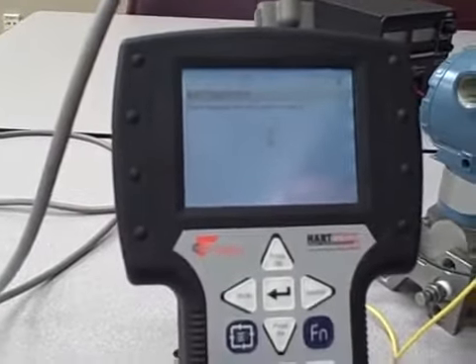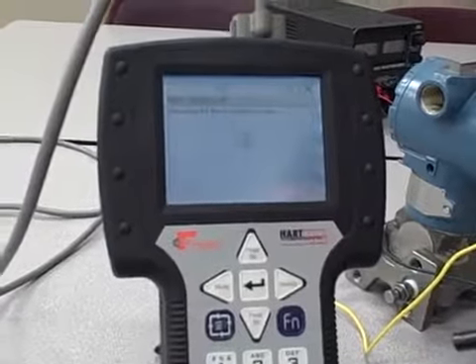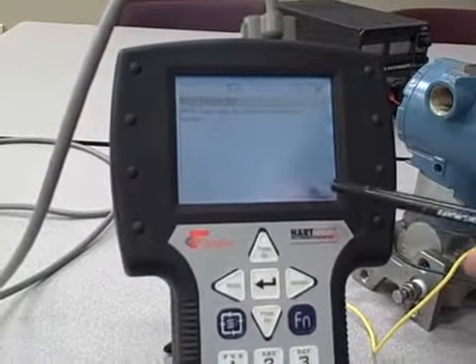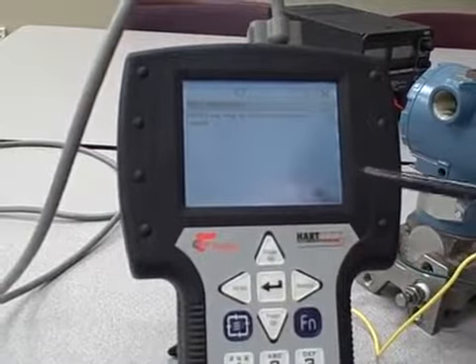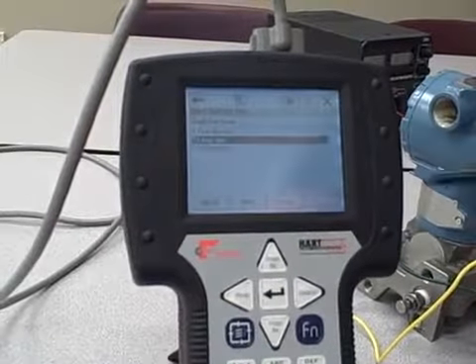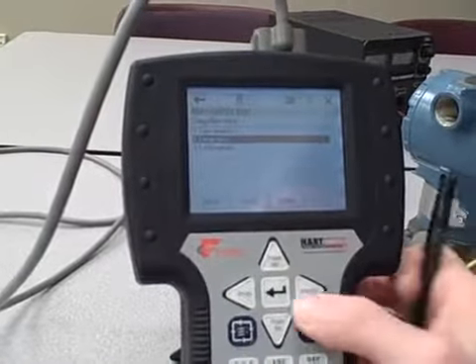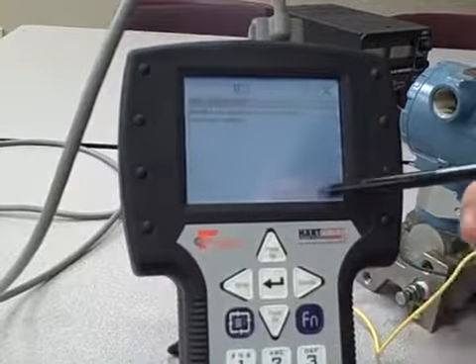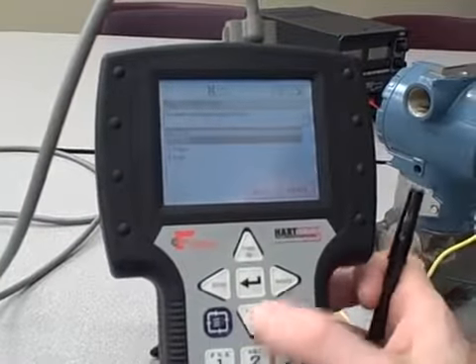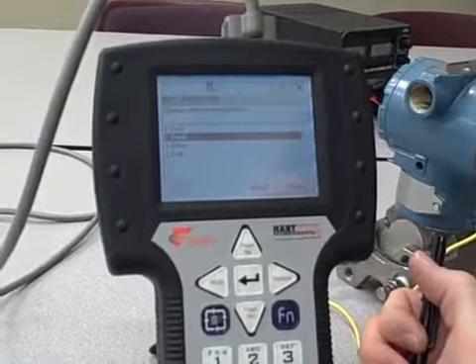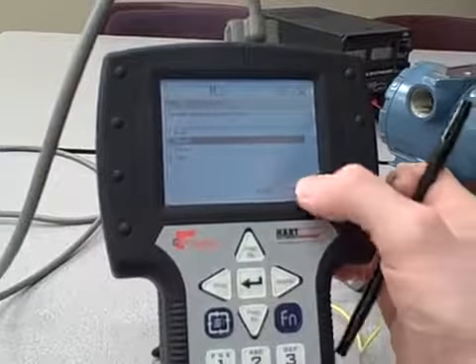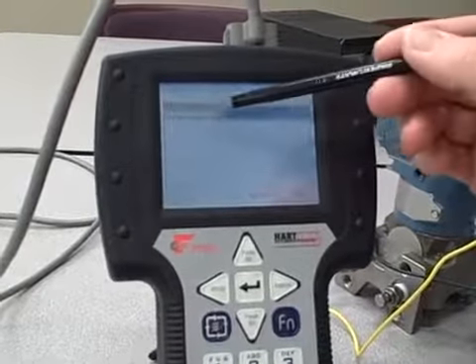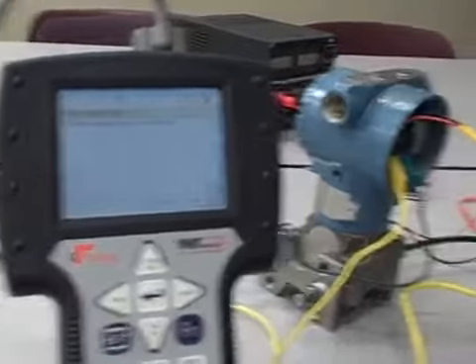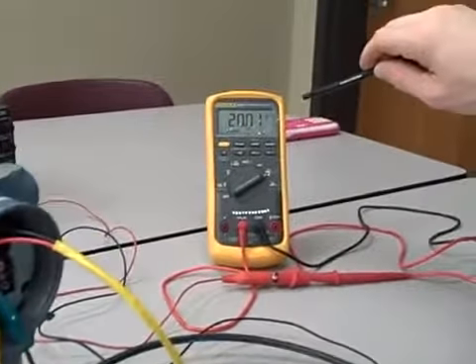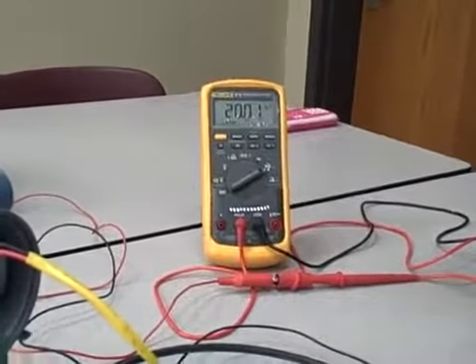Going back here, I can abort that test. Gives me another warning: loop may be returned to automatic control. I can go back into loop test and tell it to go to 20 milliamps. And it says here, field device output is fixed at 20 milliamps. And there we go. 20 milliamps indicated on our Fluke meter.